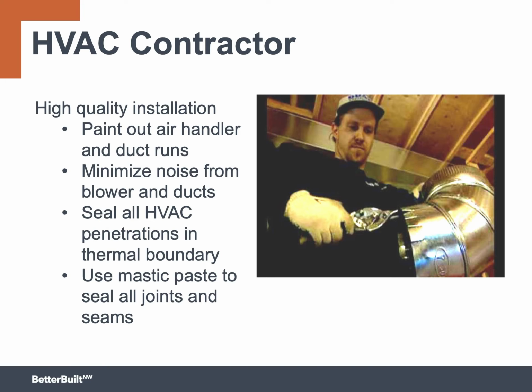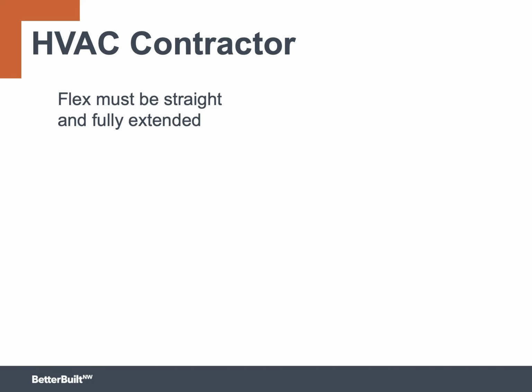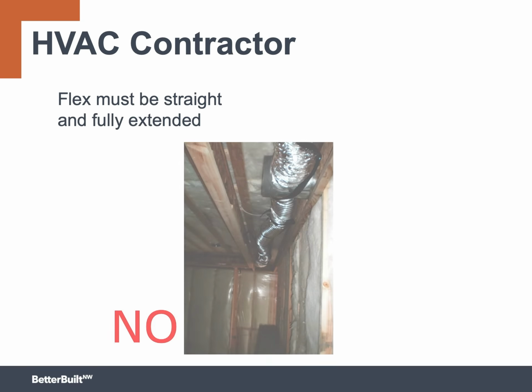Consider marking the location of duct runs with paint so that all the trades know to keep their work clear. Think about ways to reduce noise either in the selection of the duct material or in the positioning of the equipment. Seal all the penetrations that you've made in the thermal boundary, so if you make a hole, you need to seal the hole. And finally, always use mastic paste to seal all the joints, including the gores and manufactured seams. It's important to emphasize that flex duct needs to be fully extended and straight in order to minimize resistance to airflow.